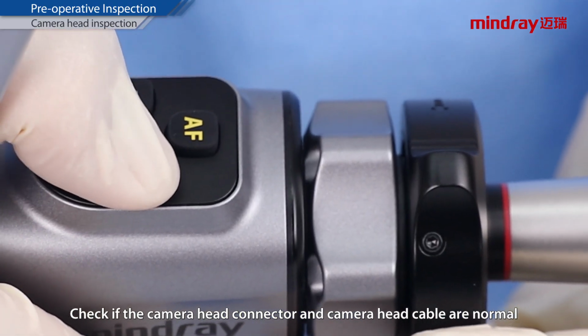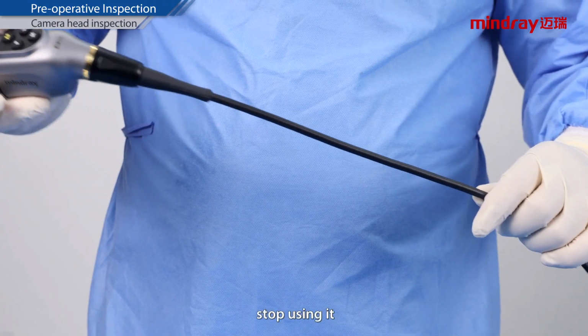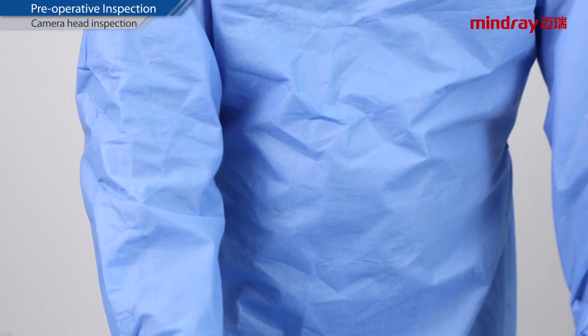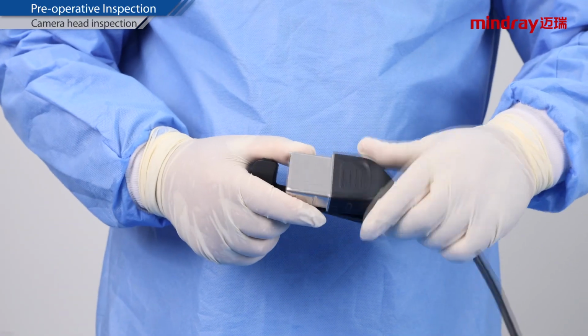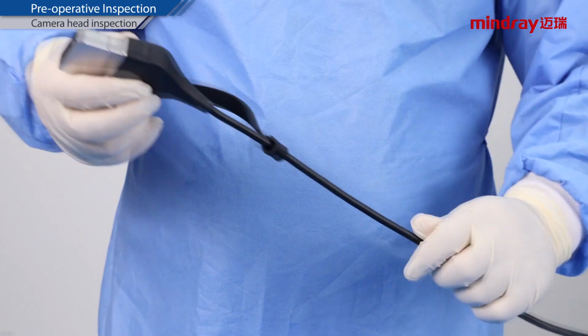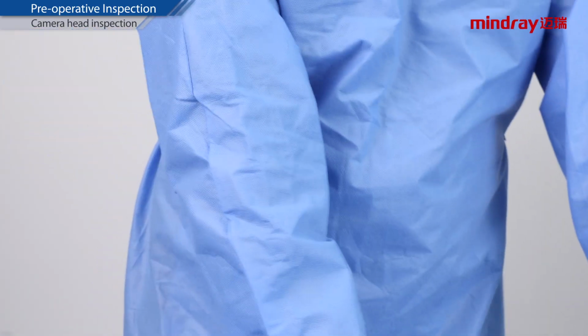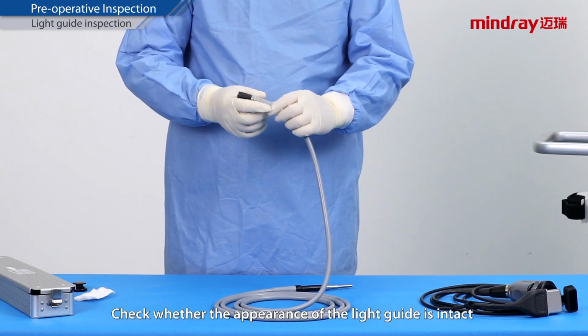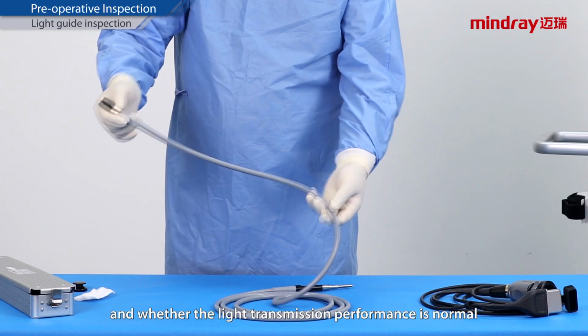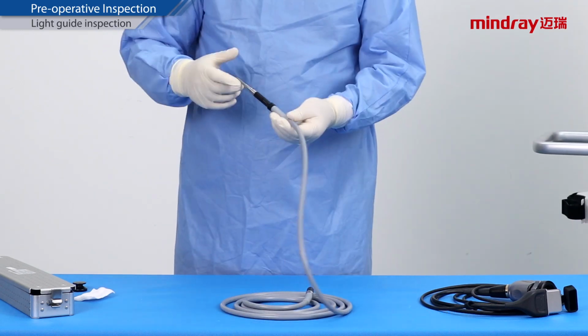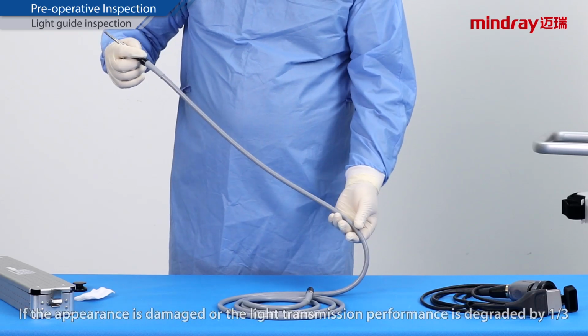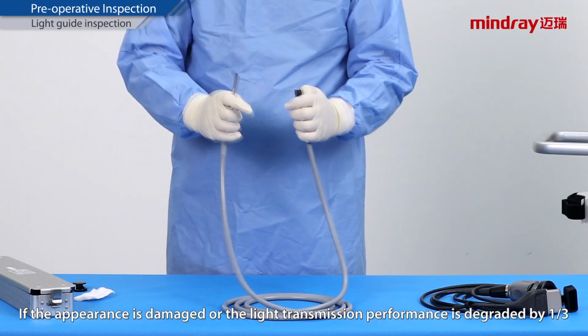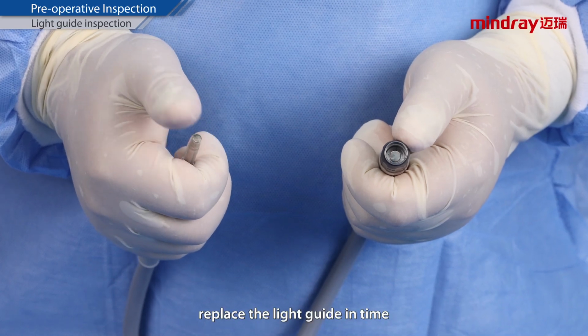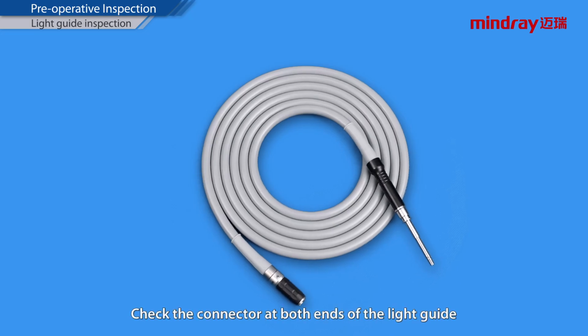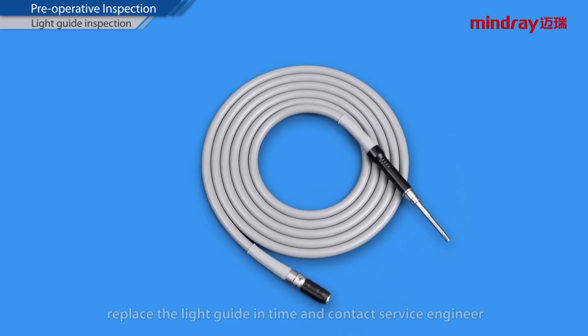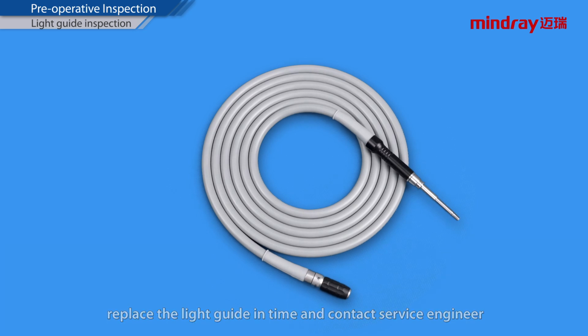Check if the camera head connector and camera head cable are normal. If not, stop using it. Light guide inspection. Check whether the appearance of the light guide is intact and whether the light transmission performance is normal. If the appearance is damaged or the light transmission performance is degraded by 1/3, replace the light guide in time. Check the connector at both ends of the light guide. If it is lost, replace the light guide in time and contact service engineer.